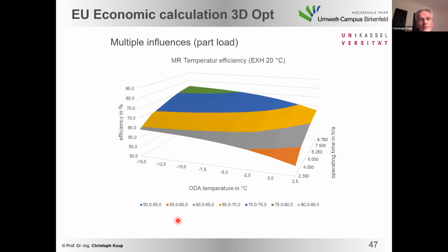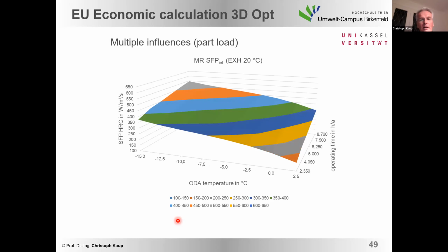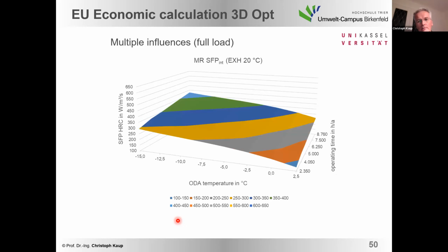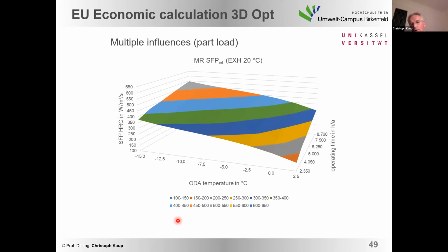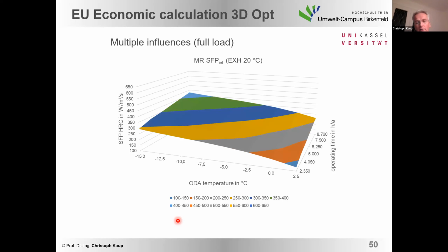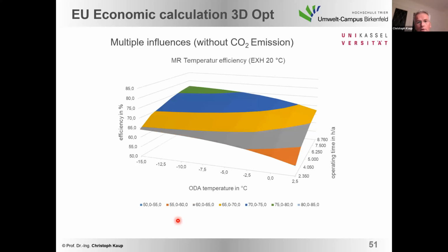Part load operation versus full load, you see there is only a small gap or difference between part load or full load operation from the thermal point of view, but not from the SFP or the electric power consumption. You see there is a big gap between full load and part load operation. Because in part load operation, it makes sense to open the SFP value, to give higher values, because this is the value for the selecting point, but the unit is driven in part load operation, and that will lead to lower actual SFP consumptions, electric power consumptions during the part load operation.